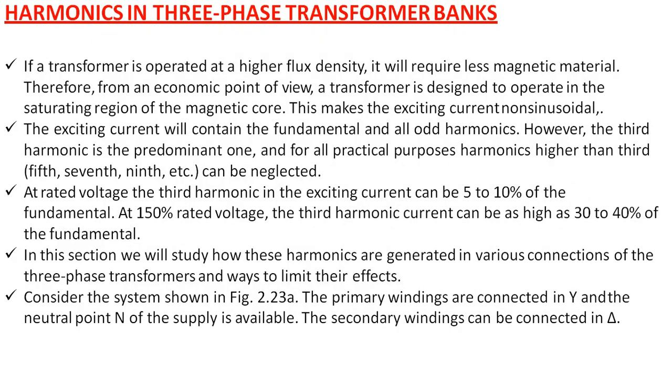Harmonics in three-phase transformer banks. If a transformer is operated at a higher flux density, it will require less magnetic material. Therefore, from the economic point of view, transformers are designed to operate in the saturation region of the magnetic core, and this makes the exciting current non-sinusoidal.